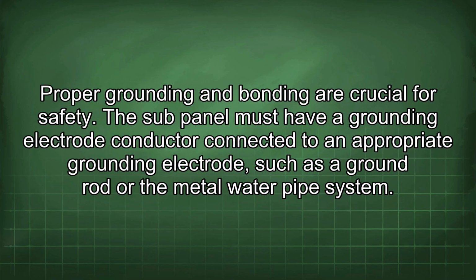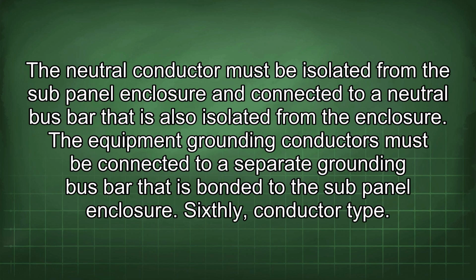Proper grounding and bonding are crucial for safety. The sub-panel must have a grounding electrode conductor connected to an appropriate grounding electrode, such as the ground rod or the metal water pipe system. The neutral conductor must be isolated from the sub-panel enclosure and connected to a neutral bus bar that is also isolated from the enclosure. The equipment grounding conductors must be connected to a separate grounding bus bar that is bonded to the sub-panel enclosure. Sixthly, conductor type.